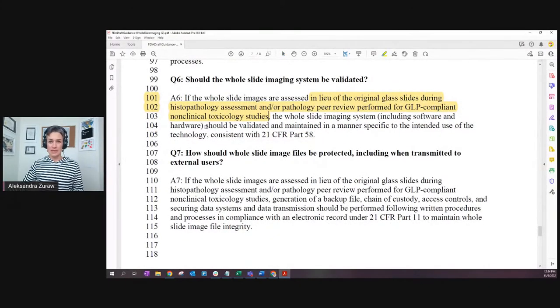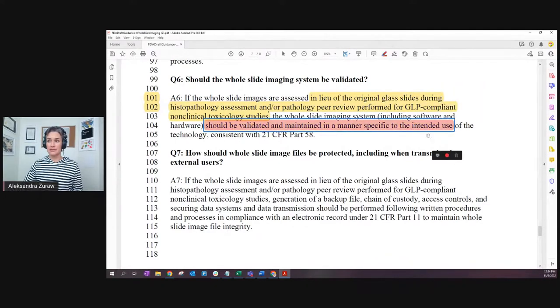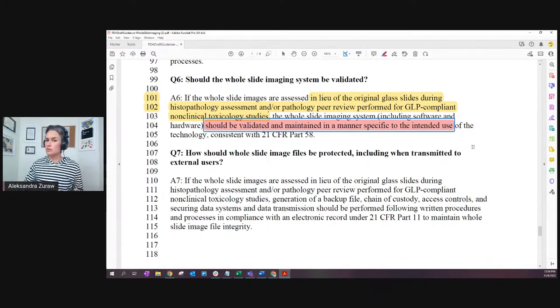FDA themselves say it should be validated and maintained in a manner specific to the intended use - and that's important as well. The intended use is what you specify in your SOPs. Basically, a system should not be used in a way it's not intended to be used.